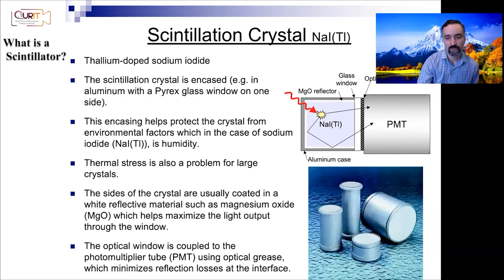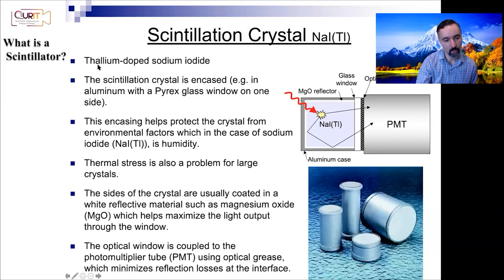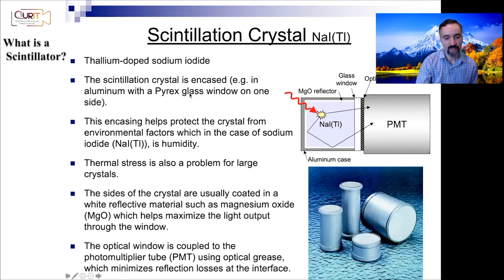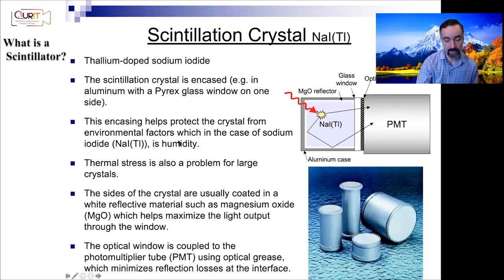Today we're going to talk about scintillation crystals. Historically there's been a lot of focus on sodium iodide doped with thallium, and we're going to talk about other scintillators too. You can see here that the scintillation crystal is encased, and the encasing helps protect it from environmental factors — in this case humidity. Thermal stress is also a problem for large crystals, and the sides are coated with reflective materials such as magnesium oxide.